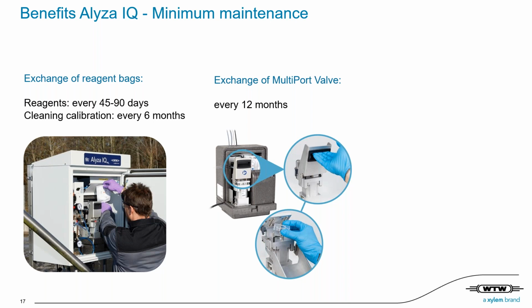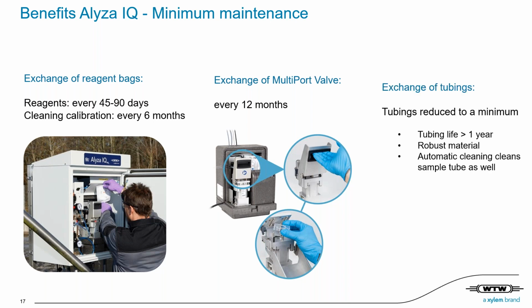Thanks to the MultiPort valve, tubings could be reduced to a minimum. Most of the tubing is only air or solution contacted, and thus a replacement is not expected. The sample contacted tubings last more than 1 year. We really improved the material and added automatic cleaning to the tube from the overflow vessel to the MPV and the photometer sample tube, so we can extend the lifetime of these tubings.